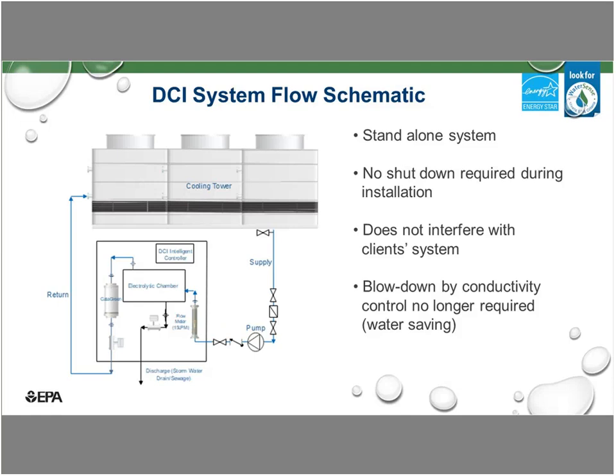We just pipe through from your infill in your cooling tower, draw the water through, and then push it through our system and return it back. Like I say, once every hour or so, we do a regeneration of the electrode where we blow down. So definitely, a conductivity meter will no longer be needed.